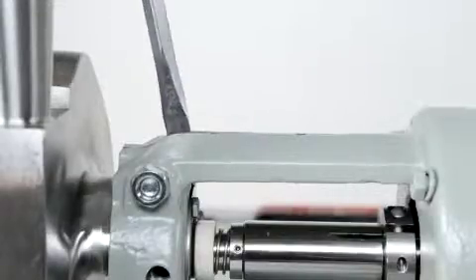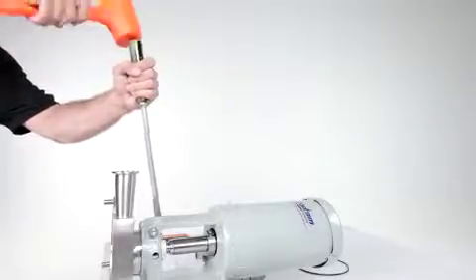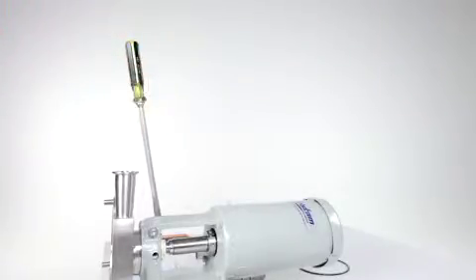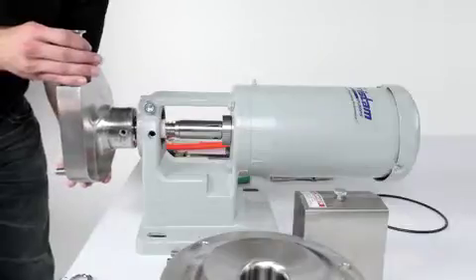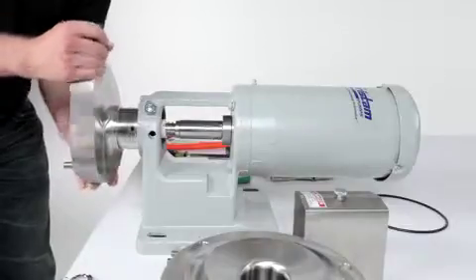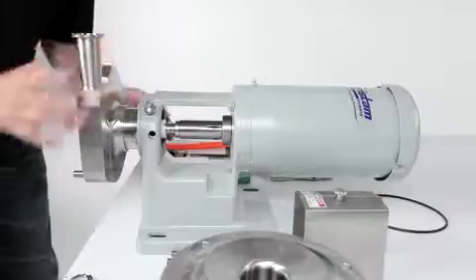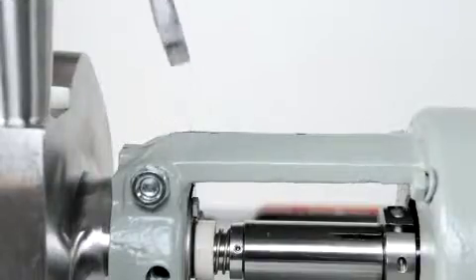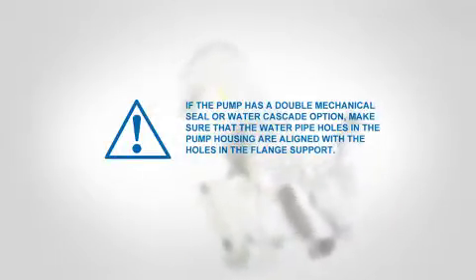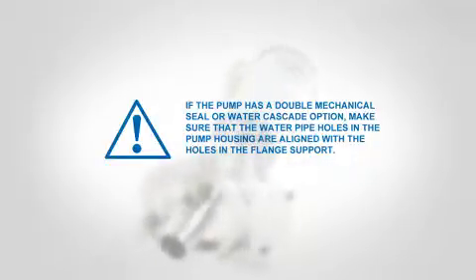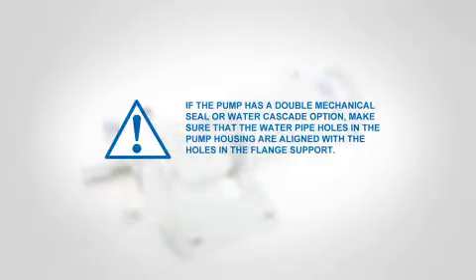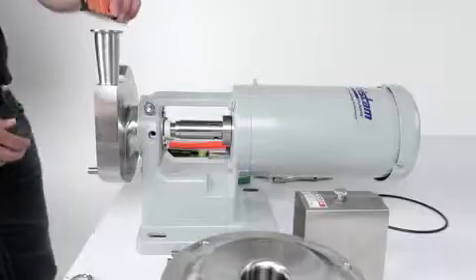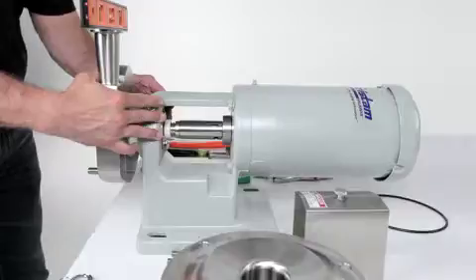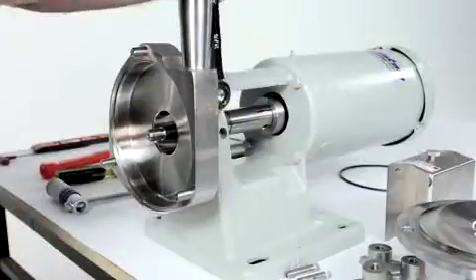If the pump housing does not slide into the flange support easily, widen the flange support by driving a screwdriver into the slot on top. Slide the pump housing all the way into the flange support until the shoulder of the housing is against the flange support. Remove the screwdriver. If the pump has a double mechanical seal or water cascade option, make sure that the water pipe holes in the pump housing are aligned with the holes in the flange support. While holding the pump housing against the flange support, tighten the clamping bolt in the flange support.